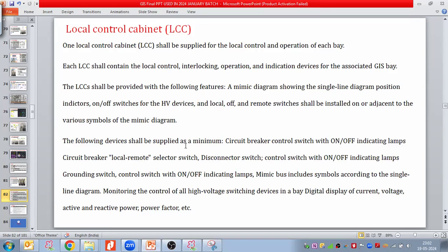The following devices shall be supplied as a minimum: breaker control switch on or off with indication lamp, breaker local-remote selector switch, disconnector control switch on-off with indication lamp, ground switch control switch with on-off indicating lamp, mimic bus including symbols according to the single line diagram, and monitoring and control of high voltage switching devices with digital display of current, voltage, active and reactive power, power factor, etc. So all the bay control we do with the help of the local control cabinet.